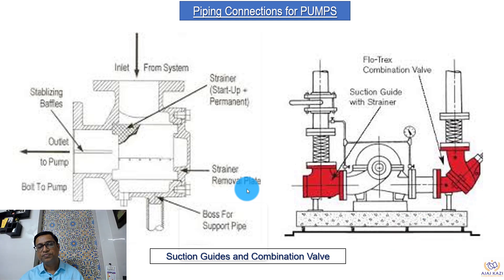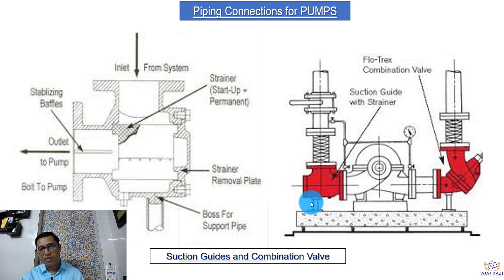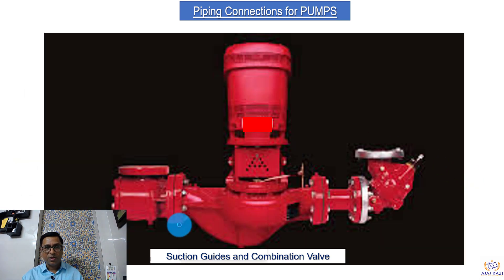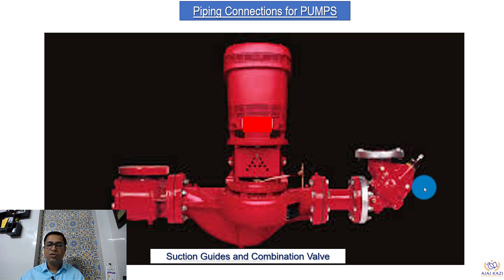One more thing coming now is that Y-strainers and NRVs are getting combined. We now have a suction guide instead of a Y-strainer, which is directly connected to the pump, and we have a combination valve which acts as an NRV plus isolation valve. This is the new development coming in — the suction guide and the combination valve. This saves a lot of joints in the piping because two things are replaced by one, and secondly the space requirement is really reduced. So this is the advantage.